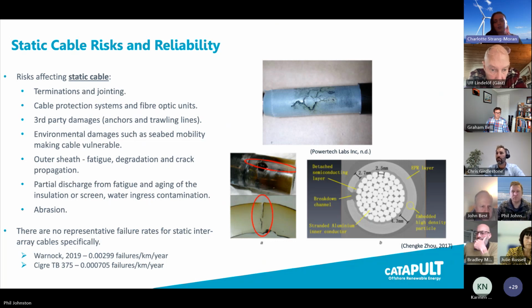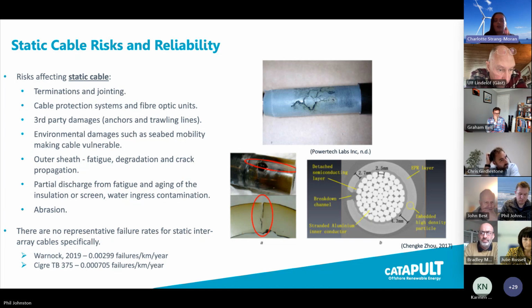So now we'll move on to some of the challenges that we've seen through risks. There are a number of risks that affect static cable. These include a high number of termination and jointing failures. Cable protection systems and fibre optic unit failure modes have led to multiple large-scale repairs in the past, as we can see in some 4C data, as well as we know in the public eye on the cable protection issues that we had a few years ago. Third-party damages from anchors and trawling lines, environmental damages such as seabed mobility, making the cable vulnerable. Outer sheaths can also be damaged through fatigue, degradation, and crack propagation. And partial discharge can affect the cable from fatigue and aging of the insulation or screen, and water ingress contamination, and of course abrasion.